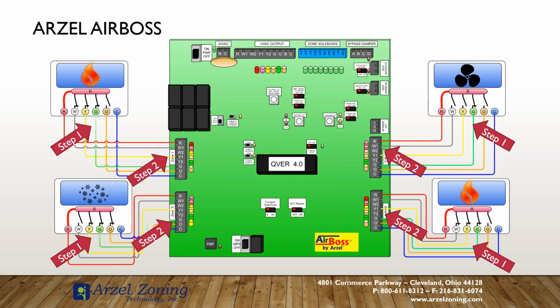Now, the Arzel panel is really simple to work around just to verify operation, because if I take a jumper wire and I jumper R and W1, that's a call for heat, or with the Heat Pump Pro, it's R and W.